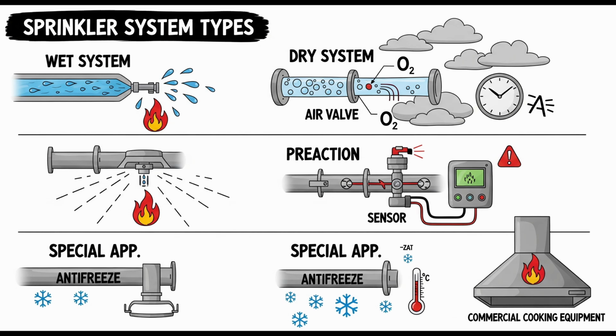And yes, we saw that tiny check valve hole appear yet again, this time with a specific note about allowing thermal expansion bleed off. And then we examined systems tailored for very specific high-consequence hazards. We went through the detailed requirement for protecting commercial cooking equipment and ventilation systems, highlighting the need for targeted nozzle placement in hoods, collars, and ducts, the necessity of using extra high temperature-rated sprinklers, and the absolutely critical function of the automatic fuel and heat shutoff that must activate upon system operation and require manual reset.